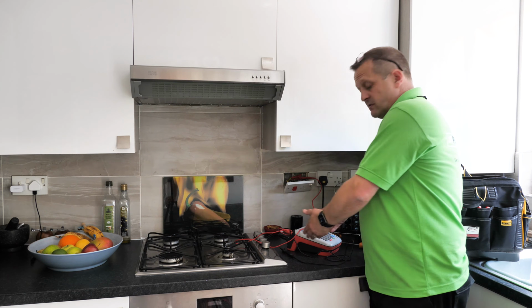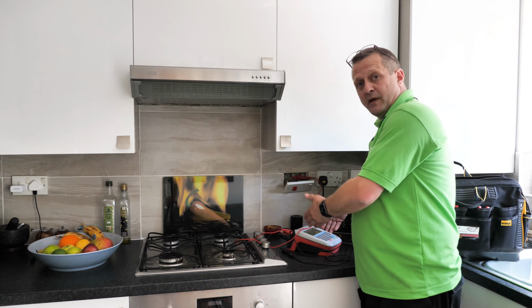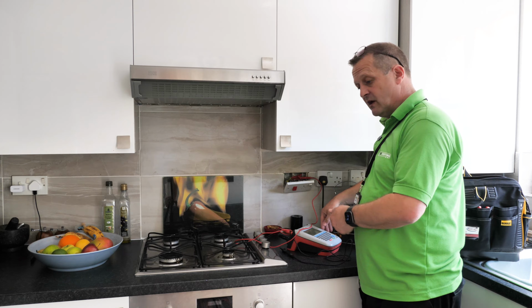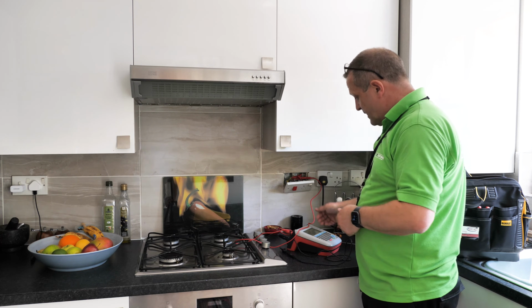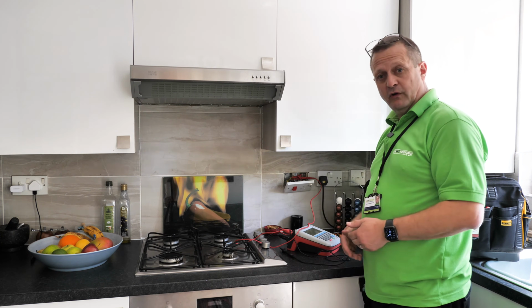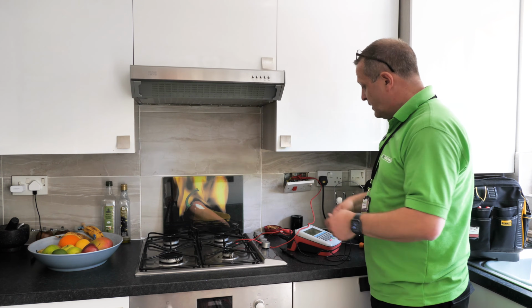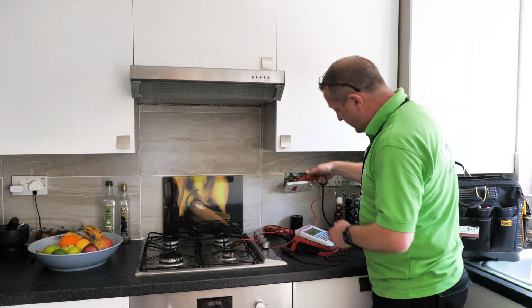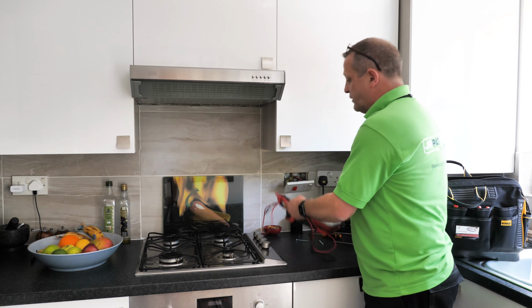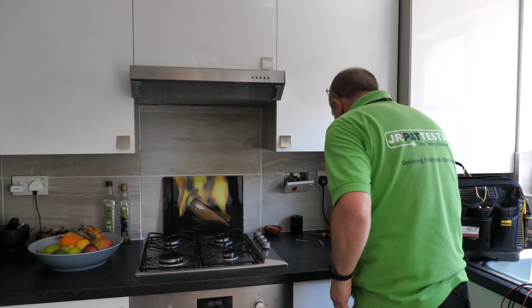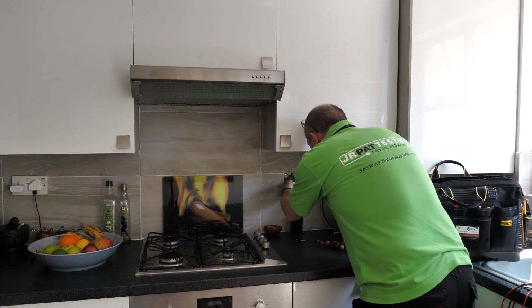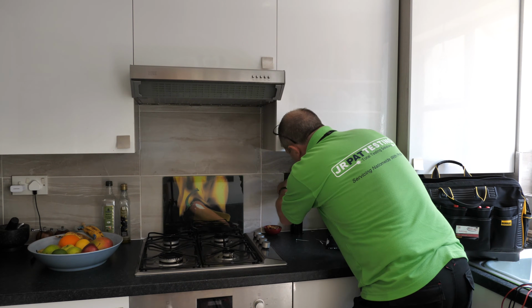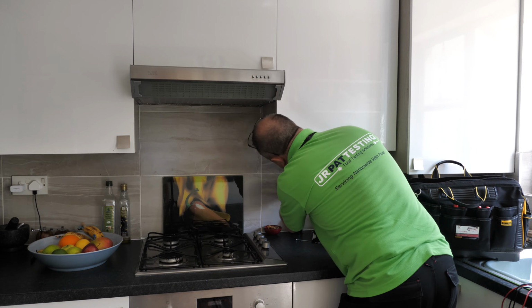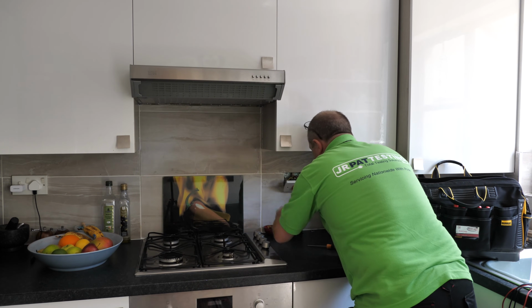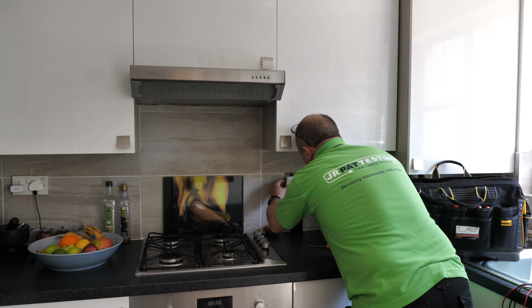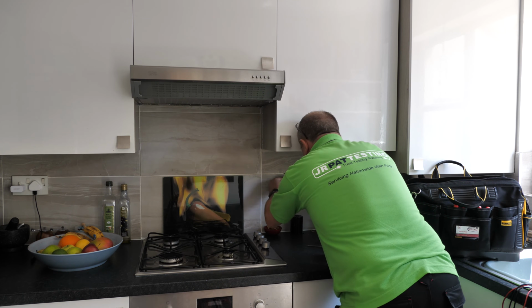So as with any other test, we fill in the details on whichever method you use, whether that's on the device itself, tablet or paper, and we would put a sticker on accordingly to show that it's passed. We then disconnect all our clips, and then we need to see about reassembling the socket. So what I'm going to do now is just reconnect the live and neutral cables, and then all we're going to do is put the socket back into its fixtures and fittings.